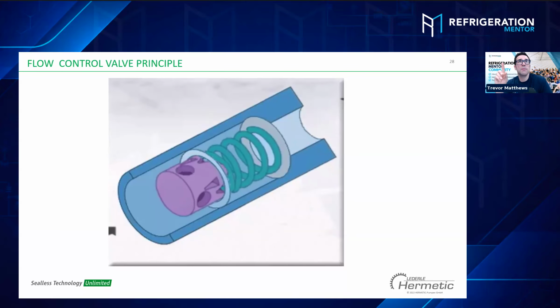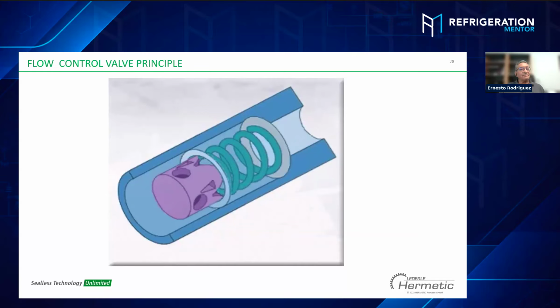And when would someone say, man, I should be using these versus not using these? A special application where you have multiple tunnels, multiple coils, multiple heat exchangers. In supermarket applications where I see some of these, there are hundreds of coils. So this would be in the liquid line going to it, like the supply line, the discharge of the pump. And it's to prevent this imbalance. When you have multiple evaporators, sometimes the evaporators closest to the pump are at higher pressure, and the ones far away are at low pressure. This is to balance the pressure in the system.